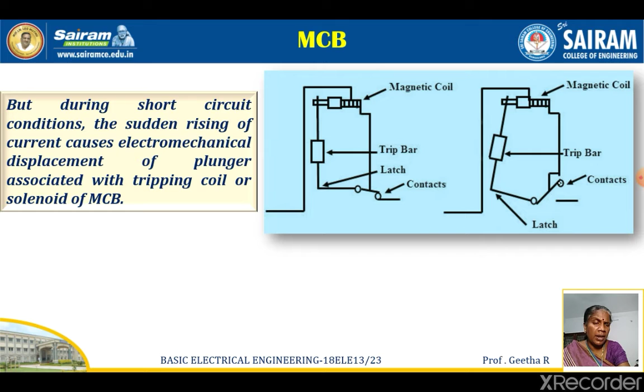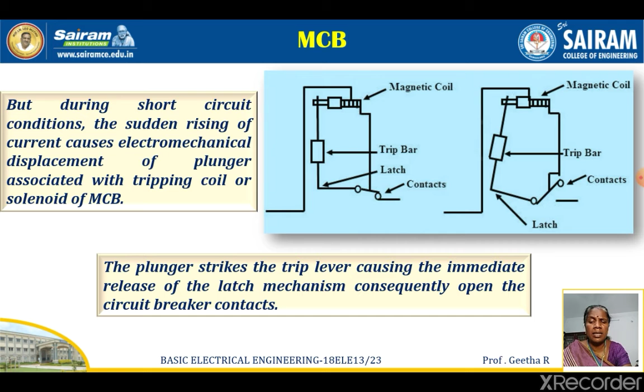that displaces this trip bar. It displaces the plunger associated with this latch mechanism that is connected to the contact. So you can see here that due to the magnetic attraction or the displacement of the trip bar, the contact is caused to open so that the MCB will be in the off position. The plunger strikes the trip lever, causing the immediate release of the latch mechanism, consequently opening the circuit breaker contacts.